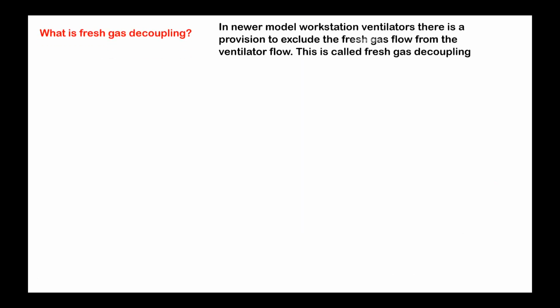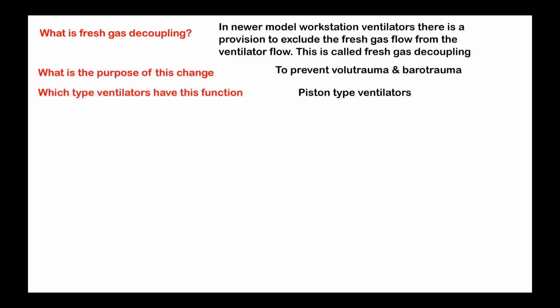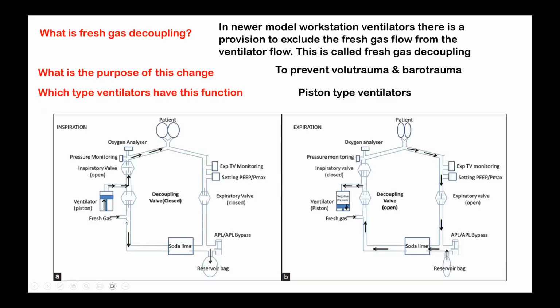Fresh gas decoupling is present in the newer workstations. What is the purpose of that? Earlier, both the ventilator driving gas as well as the fresh gas used to go to the patient, and there's a chance of barotrauma. Nowadays it is removed or separated to prevent volutrauma and barotrauma, and that is available in what is called the piston type. So this is the picture to show how fresh gas decoupling is done when the valve is open, and you can see what happens during inspiration and expiration.